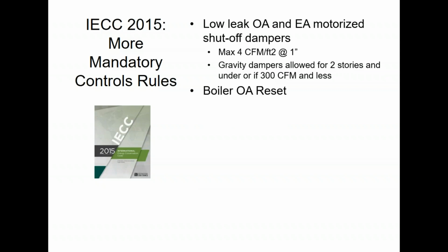There are requirements in the code for boiler outside air reset. The code does not tell you what the reset schedule needs to be. I guess you could reset it from 170 to 180 supply water if you really want to. That's pretty lame, right? You probably really want to go from 150 to 180 on a traditional system, and it'd be 120 to 180 on a condensing system. But from a code perspective, you just have to have outside air reset controls installed and operating on the boiler plant. The set points are up to the designer.